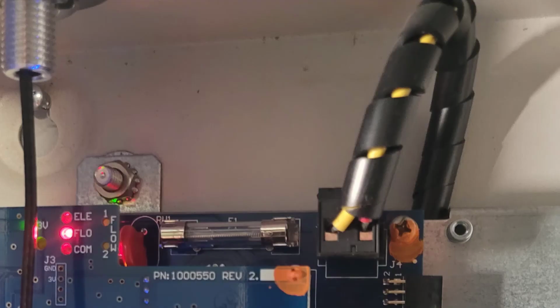Let's go from transformer to fuse. Yes, it's a 3 amp transformer, 24 volt, and that provides power to the board. Then we have a 3 amp, 250 volt fuse, which is also a slow blow fuse, or in some instances, a time delay fuse when you're trying to find these things in the store.